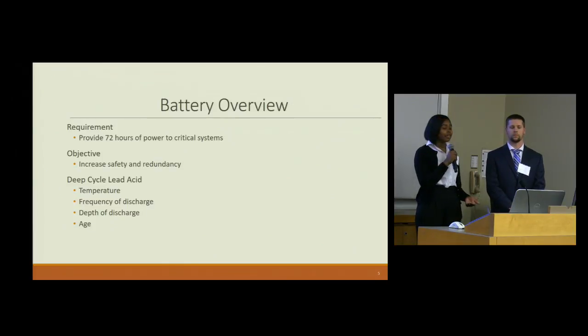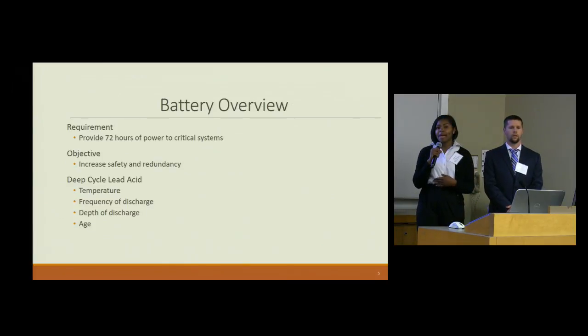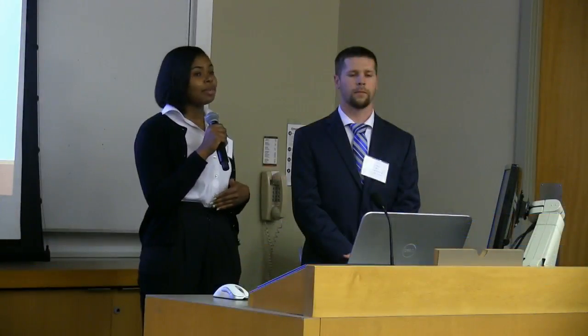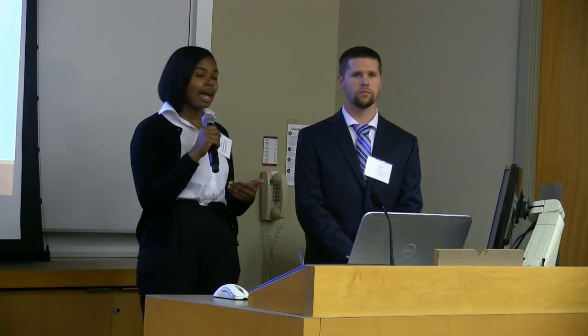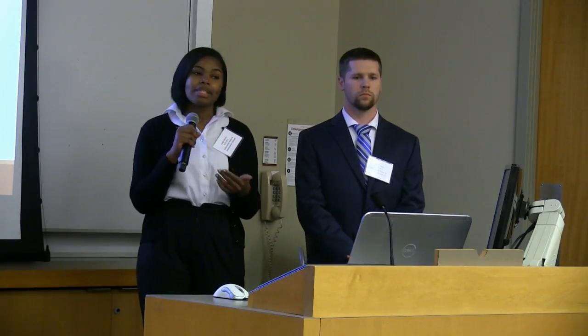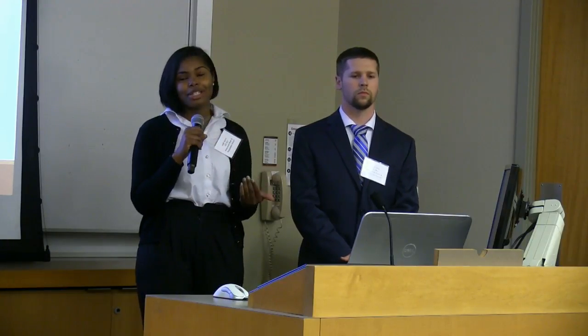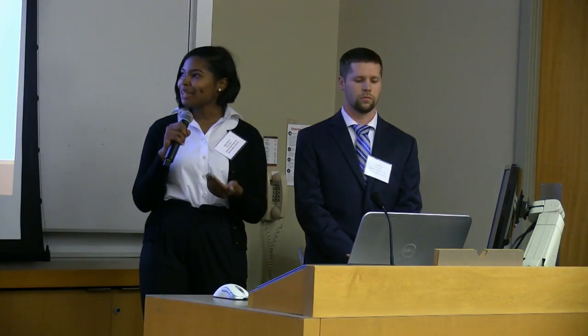Battery overview: the requirement given to us is that batteries provide 72 hours of backup power to critical systems, including lighting, SCADA, and chemical injection. As it stands, SCADA has an existing uninterrupted power supply of 13 to 14 hours, whereas lighting and chemical injection do not have a backup source of power. The purpose of adding this backup source is to increase redundancy and safety.